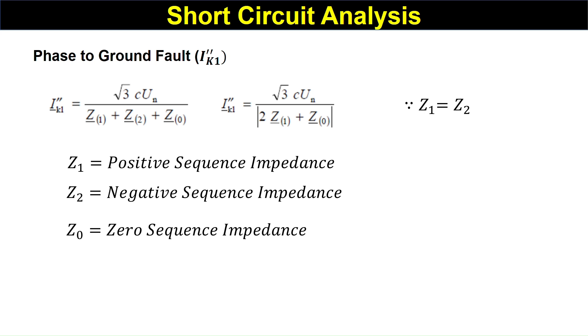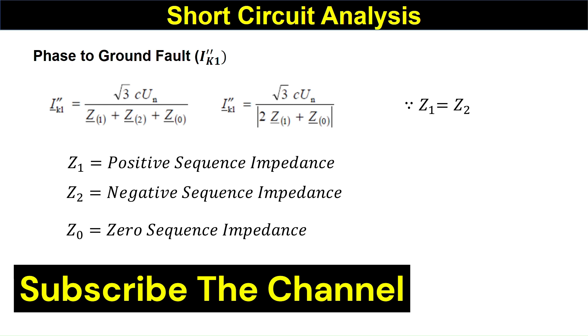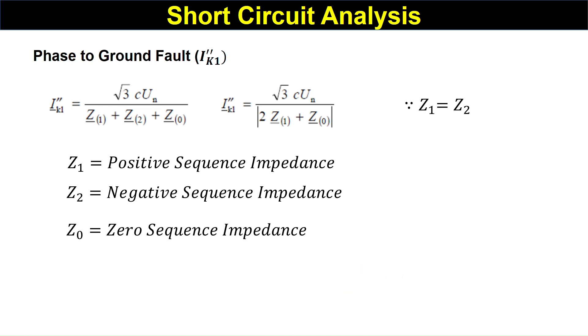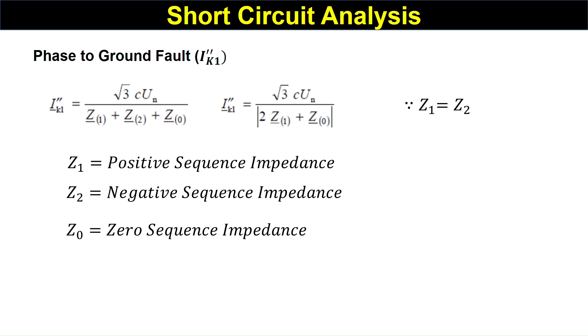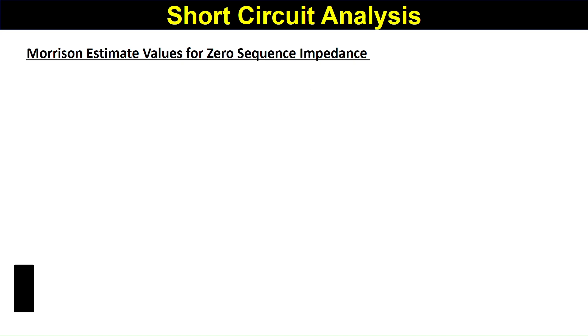To calculate the phase-to-ground fault, we need to know the zero sequence impedance. The positive sequence impedance and negative sequence impedance are equal, but we have to calculate the zero sequence impedance separately. Zero sequence impedance can be obtained from the manufacturer for machines, transformers, generators, conductors, or transmission lines. If the manufacturer does not provide it, or if you are doing a preliminary short circuit analysis, then you can use estimated values.